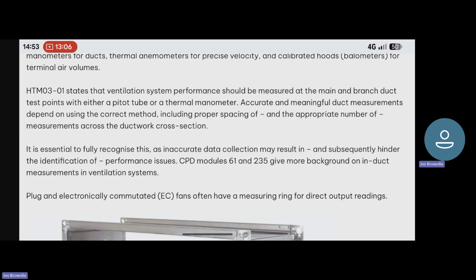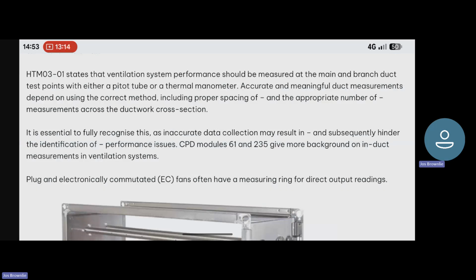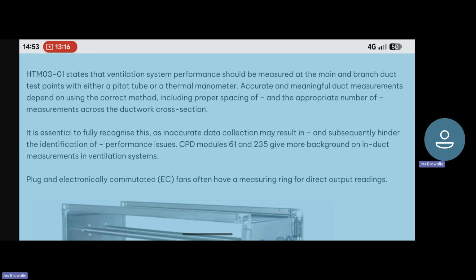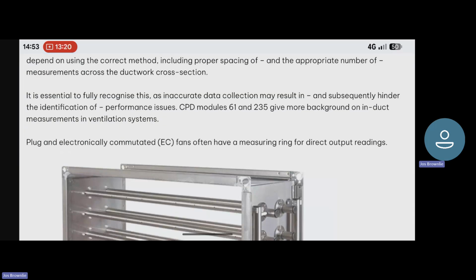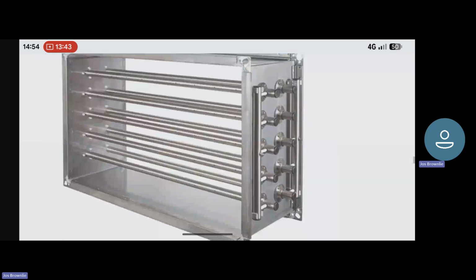Accurate and meaningful duct measurements depend on using the correct method, including proper spacing of and the appropriate number of measurements across the ductwork cross-section. It is essential to fully recognize this, as inaccurate data collection may result in, and subsequently hinder the identification of, performance issues. CPD Modules 61 and 235 give more background on in-duct measurements in ventilation systems. Plug and electronically commutated, or EC, fans often have a measuring ring for direct output readings.